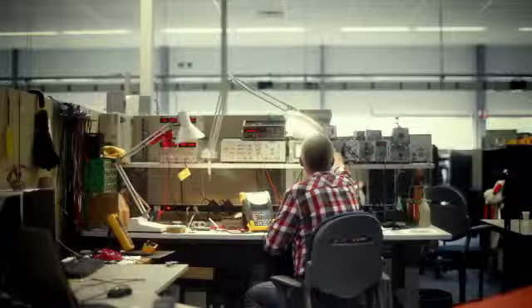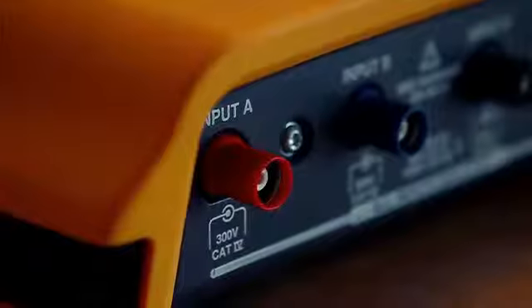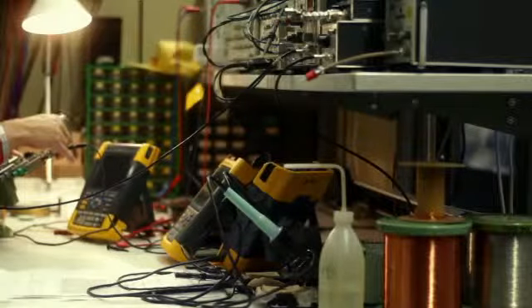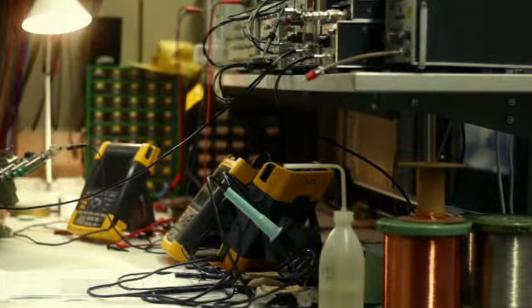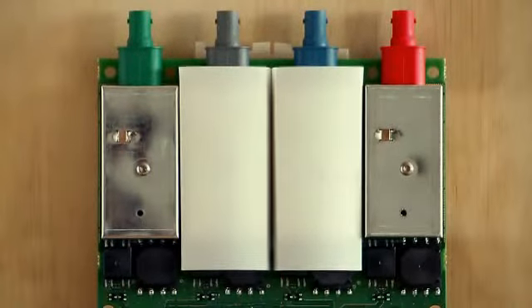The old instrument was suitable for category three. What we now did was make this instrument suitable for category four. That means you need larger clearances between conductors in your instrument. And also we had to make it narrower to comply with the four channel demand. So you have a problem.